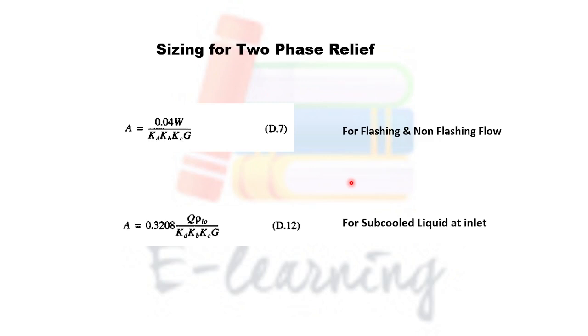If the relieving fluid is two-phase, we have to use different equations. API 520 also provides equations for two-phase fluid. For flashing and non-flashing flow we would use equation D.7, and for subcooled liquid at inlet conditions we would use equation D.12. All these equations can be found in API 520 Part 1.